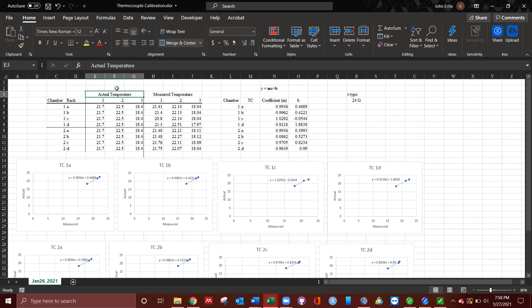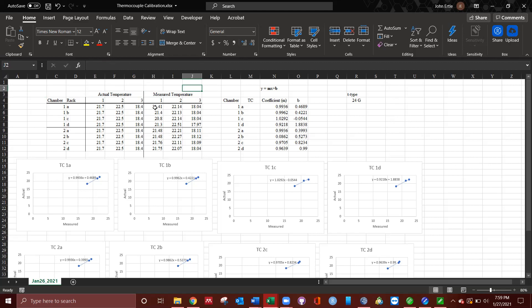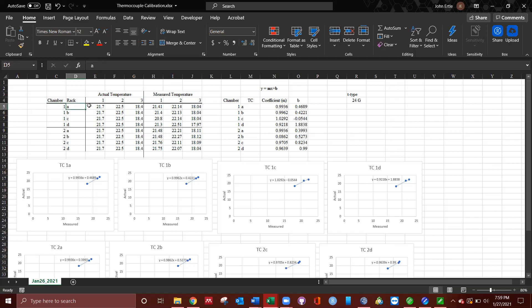In which case, this actual temperature column here is the temperature which I want to calibrate towards, and the measured temperature is the thermocouple measurement. Fine wire can give us pretty good accuracy up to two tenths of a degree. So what we have here is the tenths place, while the actual temperature is 21.7 on the thermometer, 21.41 is my measured temperature from the thermocouple. I have two chambers, four racks, meaning four different thermocouples that I'm trying to calibrate.